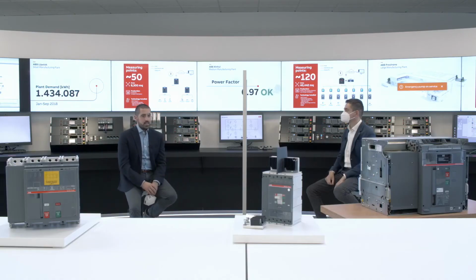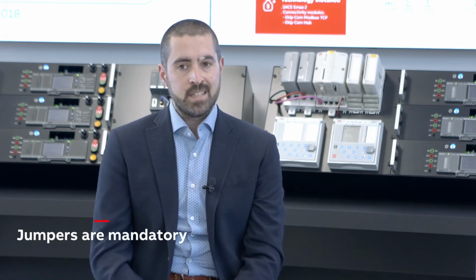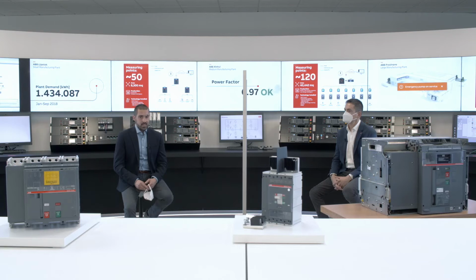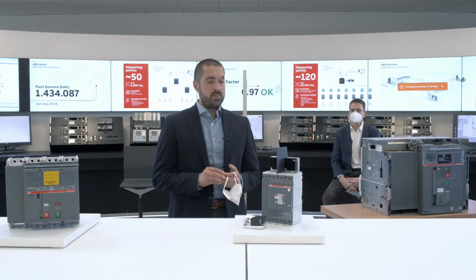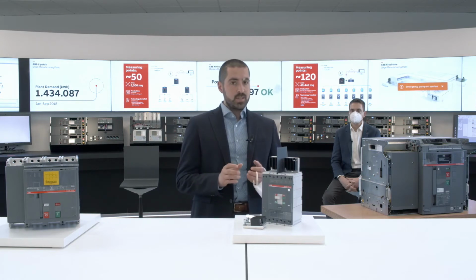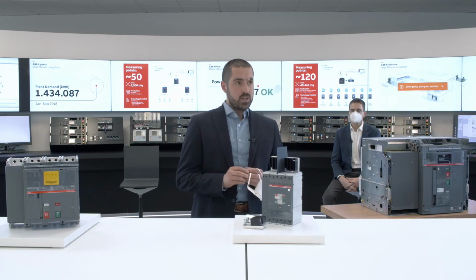Yes, jumpers are an important accessory, but sometimes they are mandatory. There are two main cases where the mounting of the jumpers is mandatory. The first one is the UL installation, because all the tests for the UL are made with jumpers. So the jumper kit is specified in the UL file, and it is mandatory to mount it in order to have a UL listed product. The second case is installations where there is high voltage in DC. In this case, the device needs to manage a high value of energy, and it is important to have great insulation between poles and also to manage the high temperatures on terminals.